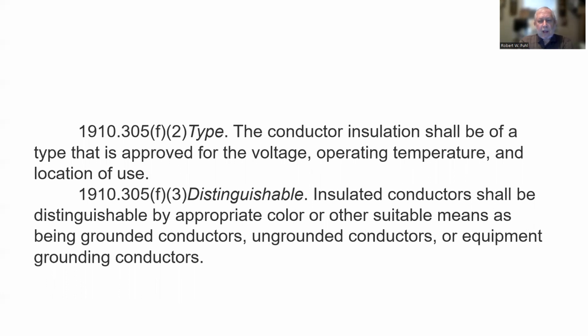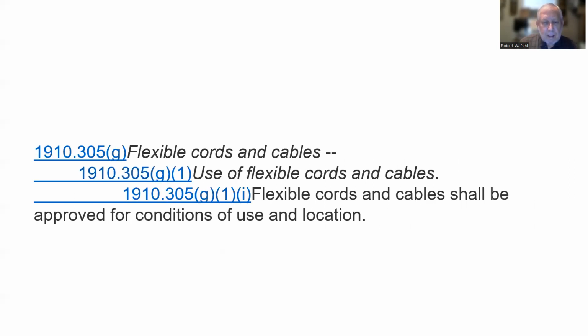The conductor insulation shall be of a type that is approved for the voltage, operating temperature, and location of use, which makes sense. Distinguishable. Insulated conductors shall be distinguishable by appropriate color or other suitable means as being grounded conductors, ungrounded conductors, or equipment grounding conductors. Flexible cords and cables. Use of flexible cords and cables. Flexible cords and cables shall be approved for conditions of use and location.